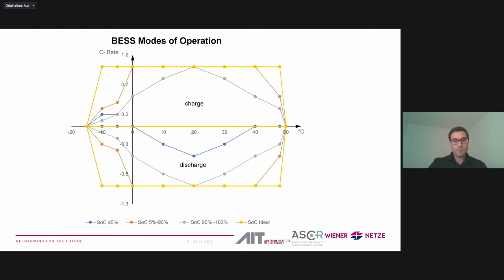But on the side, the temperature and the SOC influence the capability, which means the battery system provides the power just under perfect conditions, which is 20 degrees. If you leave this 20 degree window, the capability shrinks. So you can live with the reduction of the C rate, or you can heat or cool the systems, but then the efficiency drops.